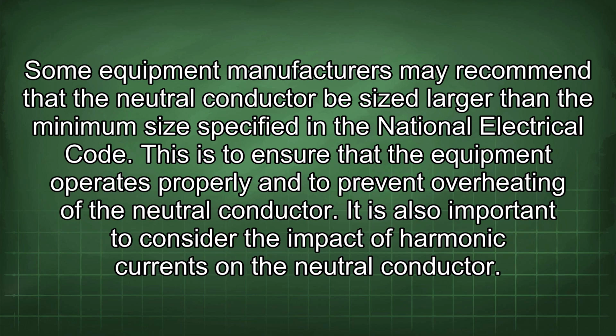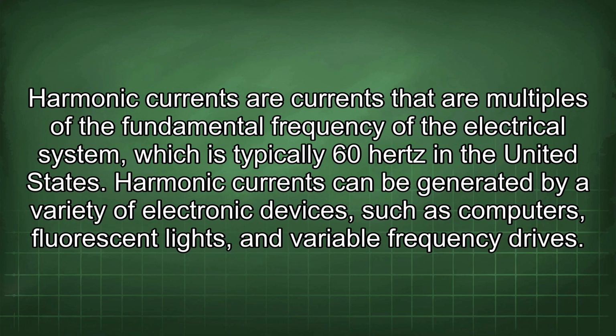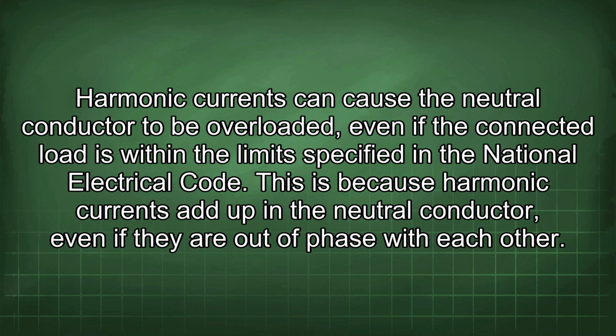It is also important to consider the impact of harmonic currents on the neutral conductor. Harmonic currents are currents that are multiples of the fundamental frequency of the electrical system, which is typically 60 Hz in the United States. Harmonic currents can be generated by a variety of electronic devices, such as computers, fluorescent lights, and variable frequency drives. Harmonic currents can cause the neutral conductor to be overloaded, even if the connected load is within the limits specified in the National Electrical Code.